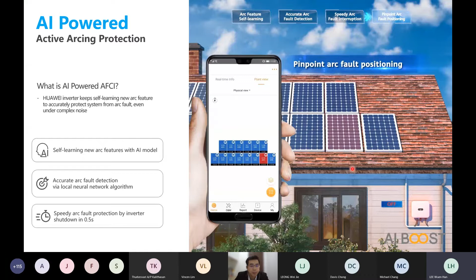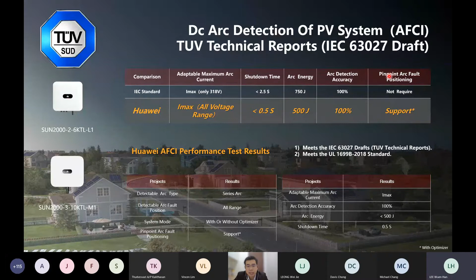Okay, whatever we have claimed and mentioned to our clients, we always back with third-party certification. As you can see here, we are in compliance with the IEC standard, IEC 63027. For now, it's still in the draft stage before its official publication, but the requirements for the IEC standard are pretty much finalized. The shutdown time for the IEC standard is less than 2.5 seconds, but our inverter is able to shut down in less than 0.5 seconds. The reason we can achieve this is because we detect the arc energy at a lower range: 500 joule, while the requirement is 750 joule. Another feature is that we can pinpoint where the arc fault actually occurs, like I showed you in the slides just now. Of course, this is with the use of the optimizer.